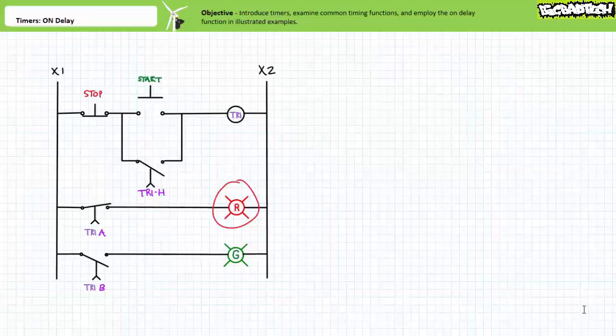I think this is a pretty fun example circuit that illustrates not only the function, but also the utility of on-delay timers. Note this particular circuit required the timer relay coil be continuously energized for a period of 5 seconds before the lights flip-flopped and the holding circuit was established. We'll examine another function called a cumulative on-delay timer in later lectures that maintains a running tally of elapsed time despite discontinuous assertion of the controlling input.